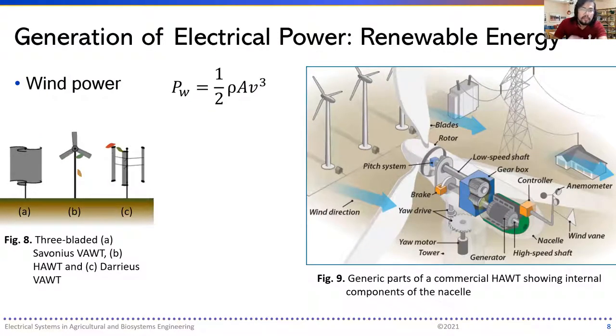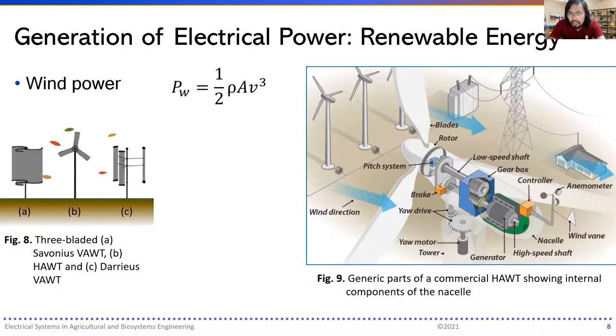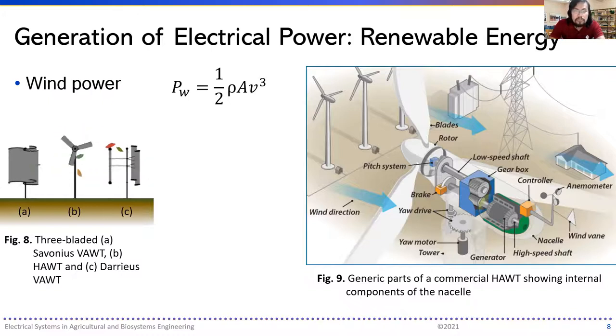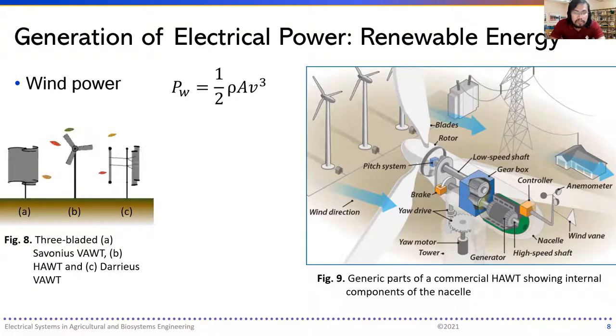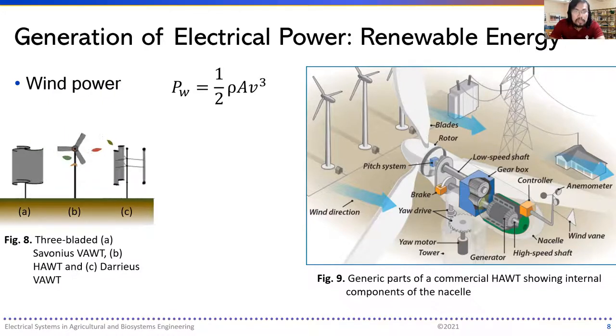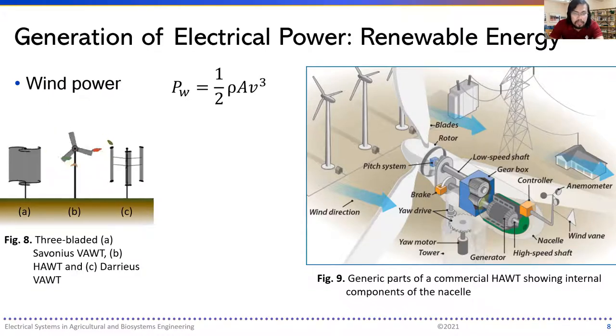Similar to water turbines, wind turbines rotate a shaft. For the HAWT, the shaft is inside a nacelle, where the slow shaft rotation is sped up with a gearbox. A difference between HAWTs and VAWTs is that HAWTs need a pitching and yawing system to position the blades along the wind direction, while VAWTs can accept wind from any direction, so there is no need for a pitching and yawing system.